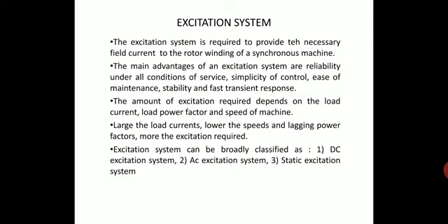An excitation system is of two types, in case more units are used: individual excitation system and centralized excitation system. In an individual excitation system, each generator is provided with its own exciter, but in a centralized excitation system, two or more exciters feed a bus bar to which the field systems of all the alternators in the power plant are connected.